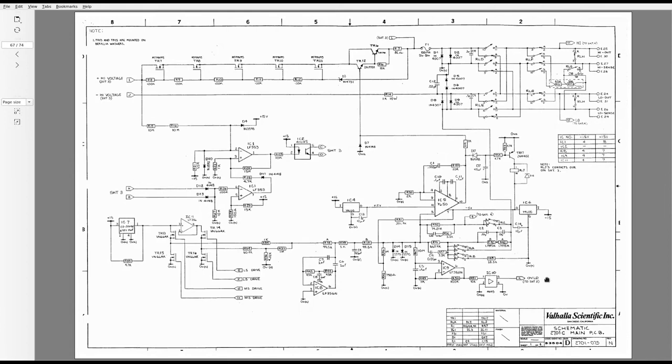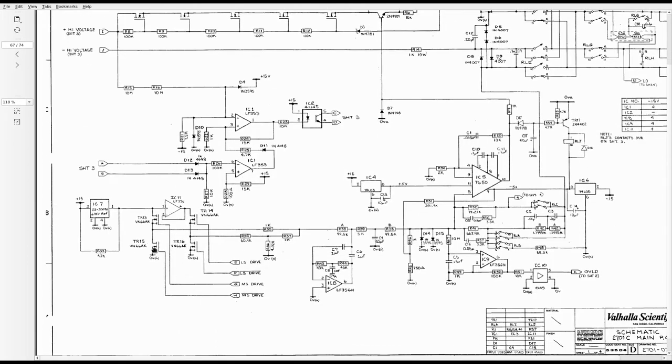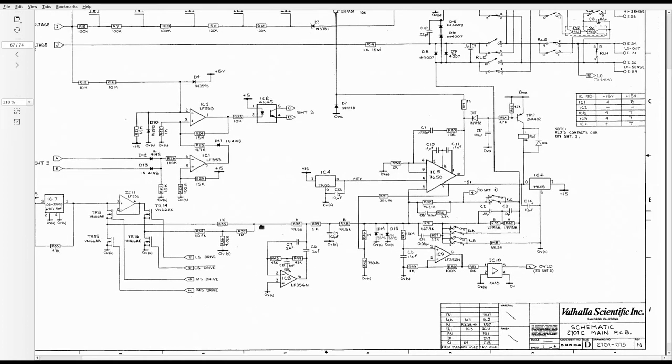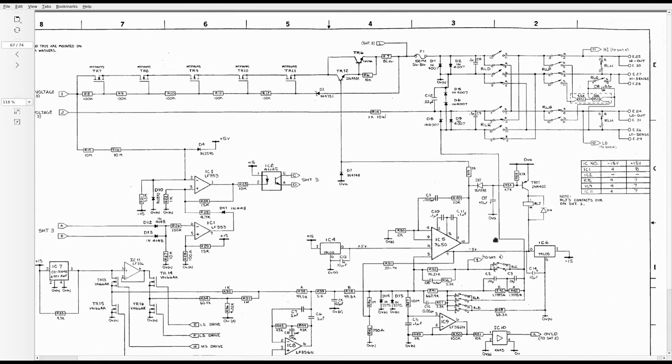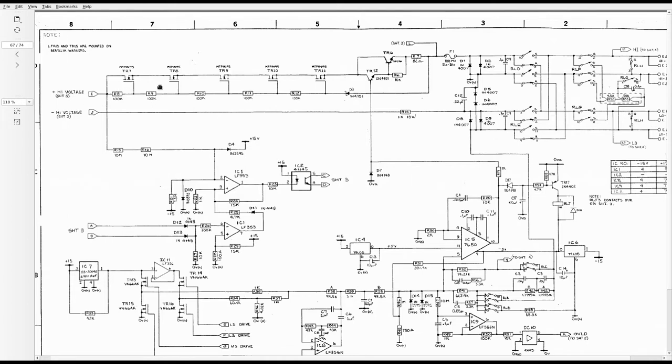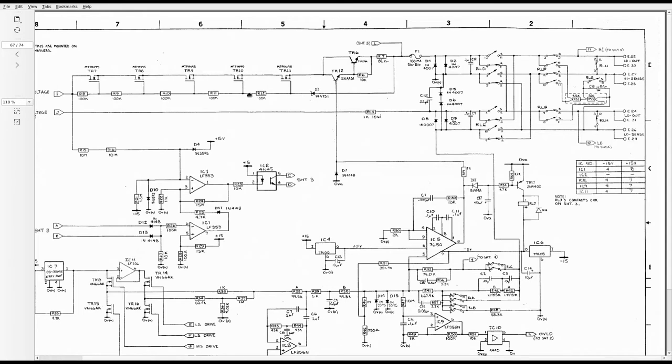Or there's this method used in the Valhalla 2701, and I think some of the Fluke calibrators do something a bit similar. I found this pretty elegant. They generate two PWM signals, both positive and negative polarity. It drives an H bridge here. This is a voltage reference. So it takes a PWM, scales both of them with the ratios. I think it's about 1,000 to 1. And then some filtering, then onto the amplifier here, and another fancy amplification with a bunch of stuff to get the high voltage output. I think it could go to 1,000 volts or something.